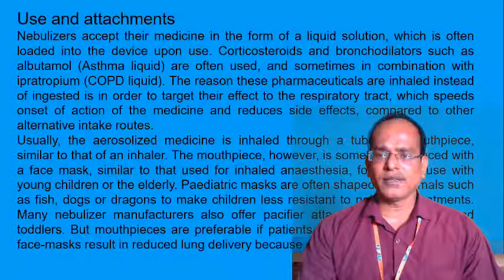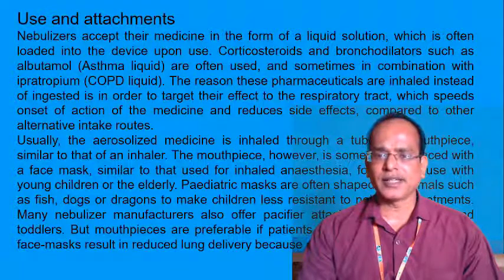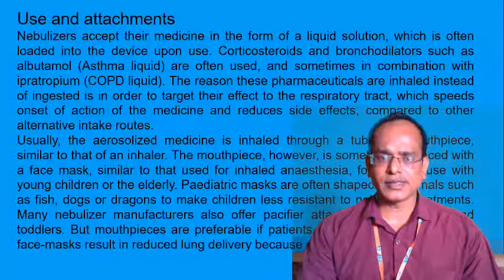Pediatric masks are often shaped like animals such as fish, dogs or dragons to make the children less resistant to nebulizer treatment. Many nebulizer manufacturers also offer a pacifier attachment for infants and toddlers, but mouthpieces are preferable if the patients are able to use them, since the face mask results in reduced lung delivery because of aerosol losses in the nose.